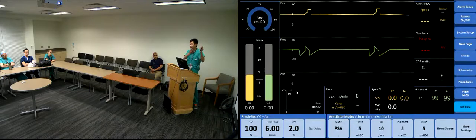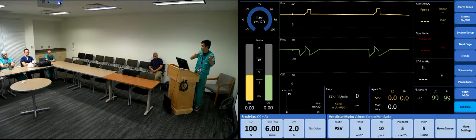And then you have your pressure support mode, which you guys are probably comfortable with by now. The key thing with the true pressure support mode is that the patient has to initiate their own breath. So the machine detects a negative flow, and once it detects that negative flow, it gives a breath, and it'll be a pressure breath, so it'll be a little square, just like your pressure control modes, okay? But we have a backup mode, and it'll back up into SIMV if the patient's not breathing and it detects that they're apneic for about a minute or something like that, okay? So those are your different modes.